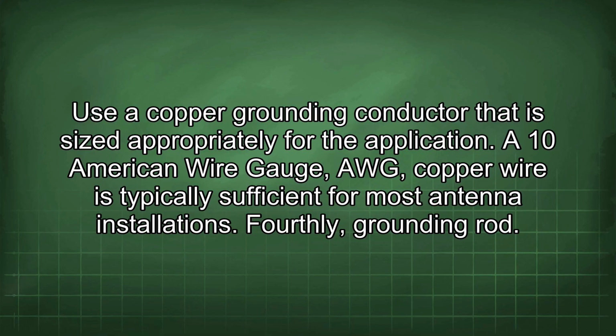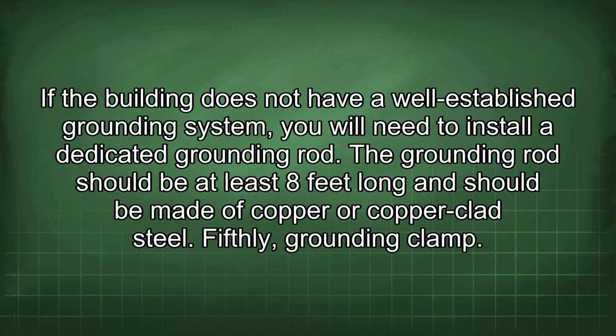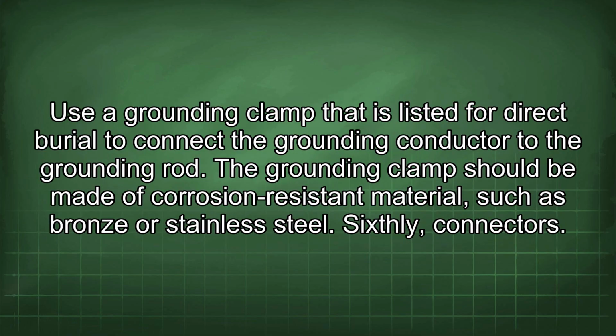Fourthly, grounding rod. If the building does not have a well-established grounding system, you will need to install a dedicated grounding rod. The grounding rod should be at least 8 feet long and should be made of copper or copper-clad steel. Fifthly, grounding clamp. Use a grounding clamp that is listed for direct burial to connect the grounding conductor to the grounding rod. The grounding clamp should be made of corrosion-resistant material, such as bronze or stainless steel.